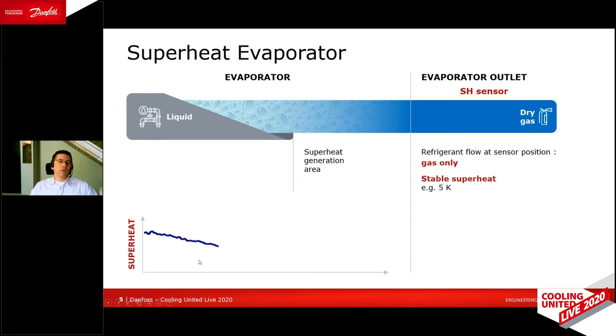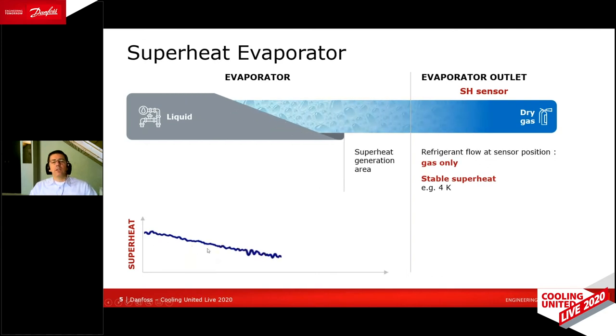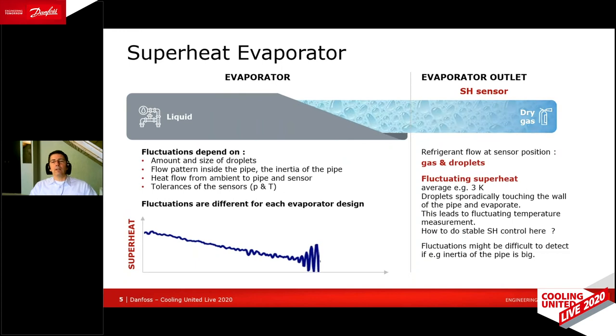Now we reduce the superheat and see it going down. We still have enough superheat generation area to produce dry gas, and the gas leaves the evaporator with a superheat of, let's say, 4 Kelvin. If we reduce even further, the refrigerant leaving the evaporator becomes a mixture of gas and some droplets. Those droplets hit the wall of the pipe leaving the evaporator and evaporate there.